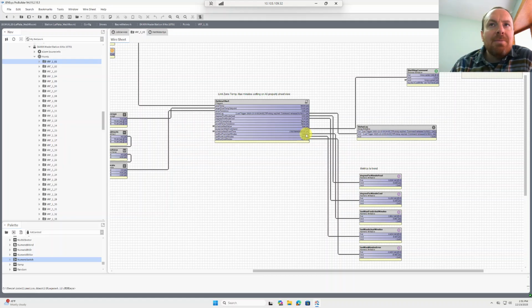The last time this block ran, it took about 6 minutes for the zone to catch up to set point. It predicted 5.96, and it actually took 6.42 is what the algorithm inside recorded, which had some error of about 30 seconds.